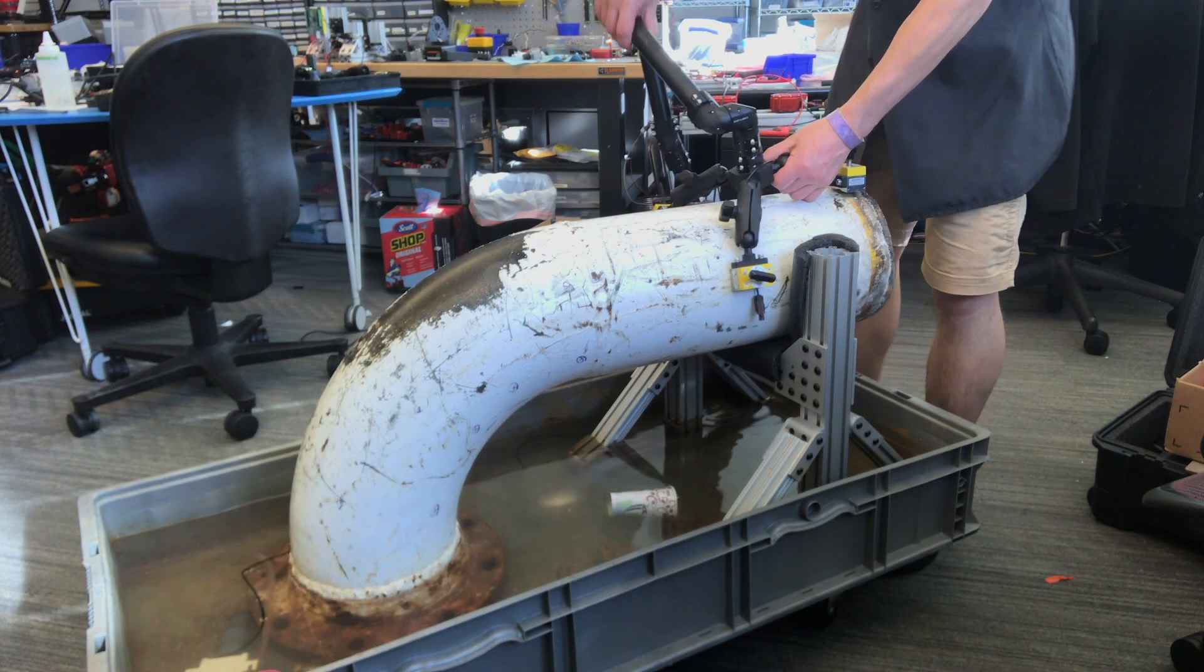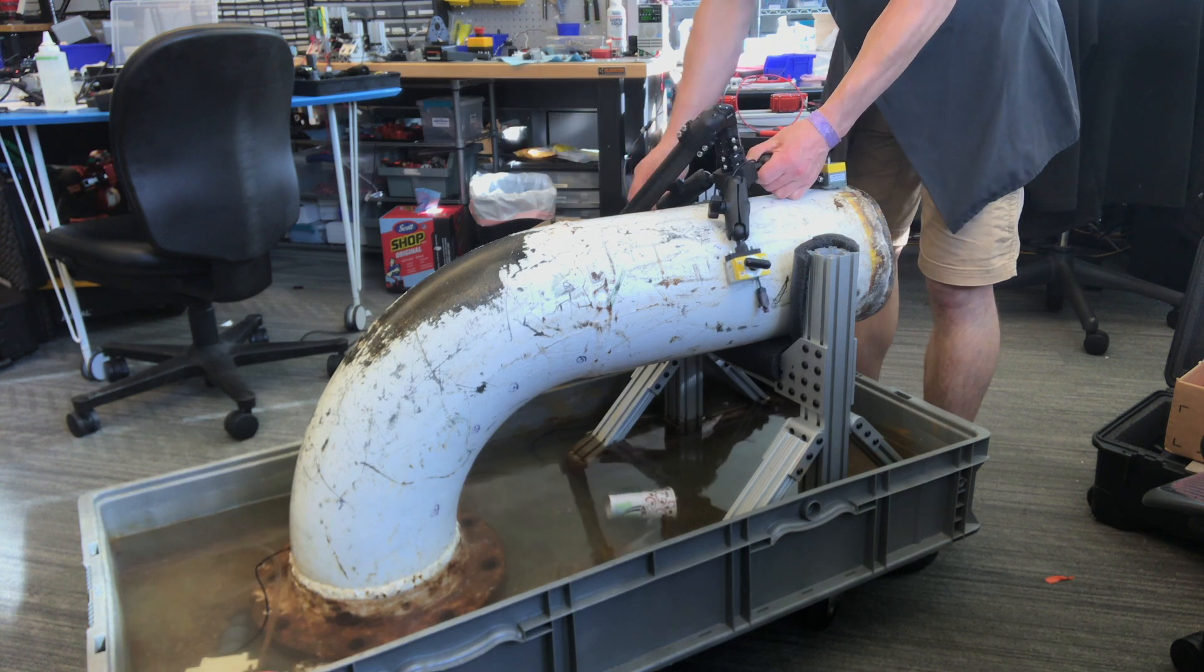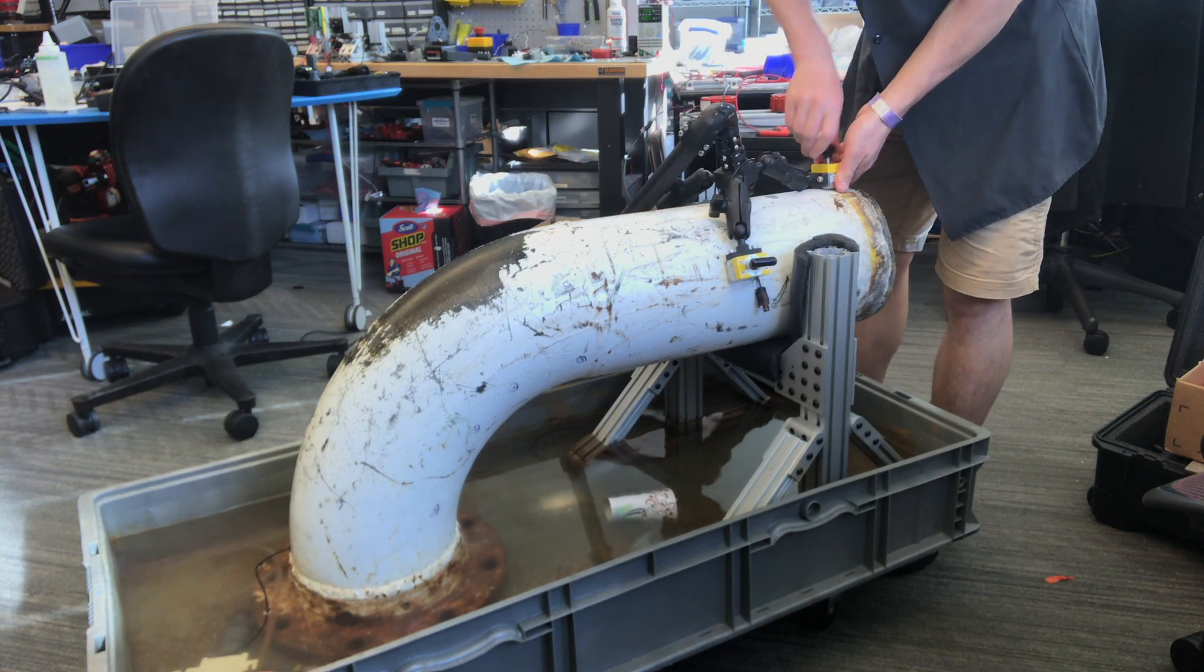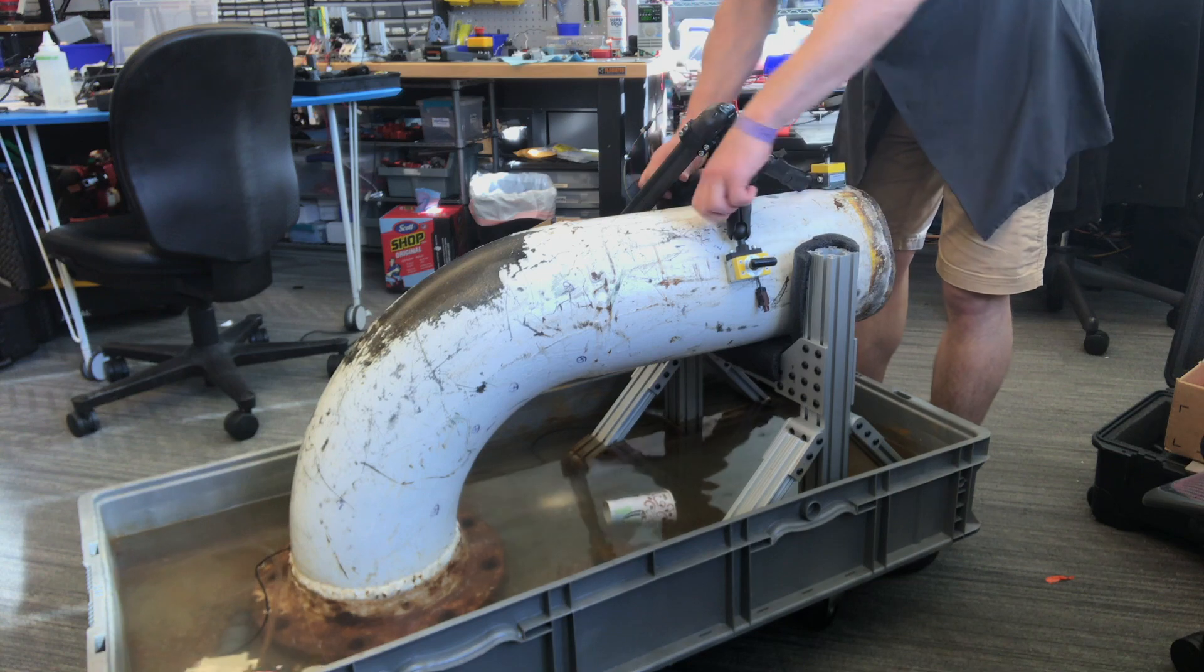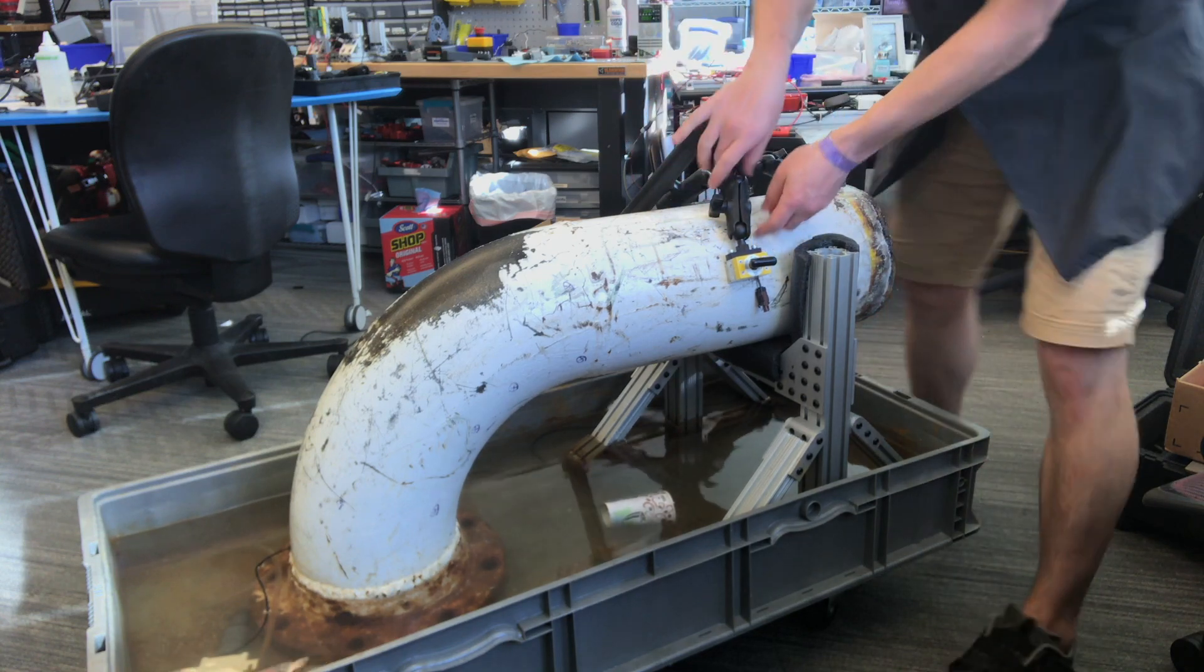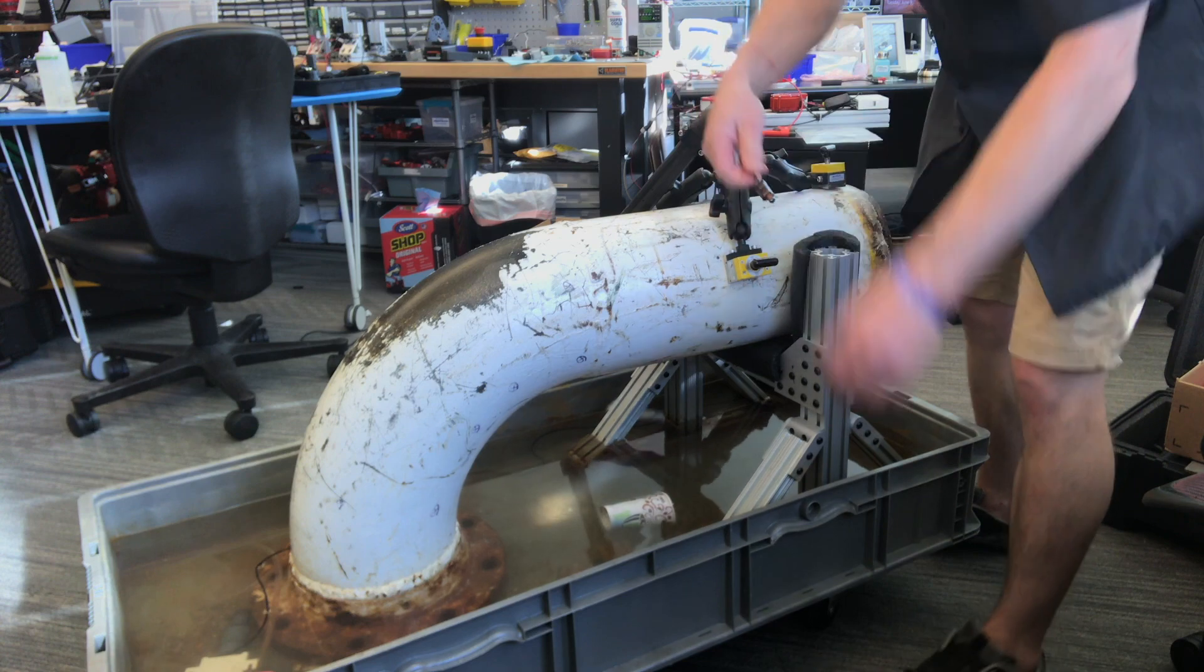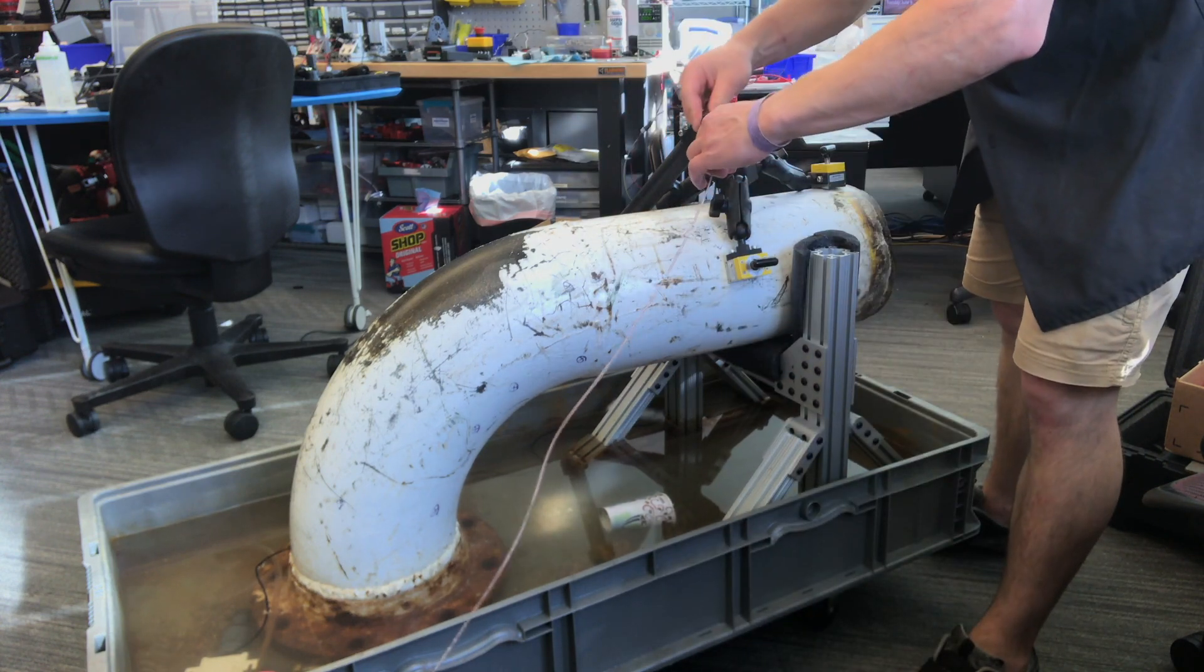To begin an inspection, the arm needs to be fixed to a surface. In this video, I'm showing clamping it to the pipe that we're going to inspect, but it can be mounted to a support or really anything else that fixes the base with respect to the asset that you're going to inspect.